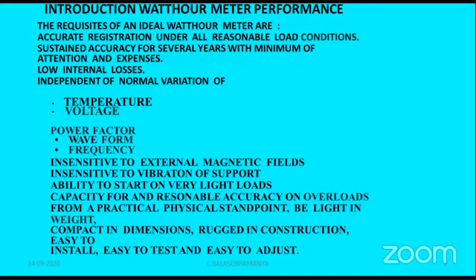It is not possible from the point of adjustments. If there are more adjustments, naturally you will be maneuvering the meter, and the meter becomes unstable. So an electronic meter need not be adjusted. It is a factory set adjustment. It is a laser trimmed arrangement where the whole meter works satisfactorily over the complete load characteristics domain. That means from 10 amps to 100 amps, it will function very accurately. So this is the introduction on the requirement of the meters.